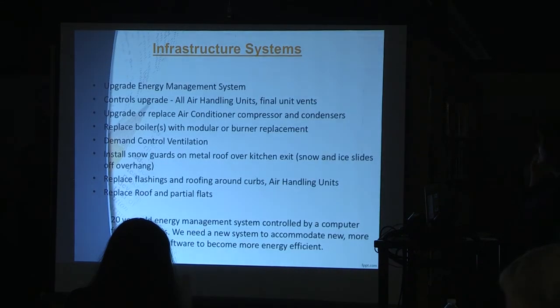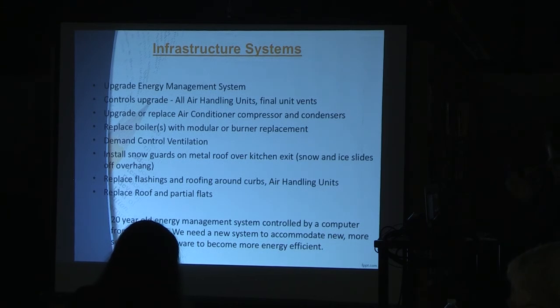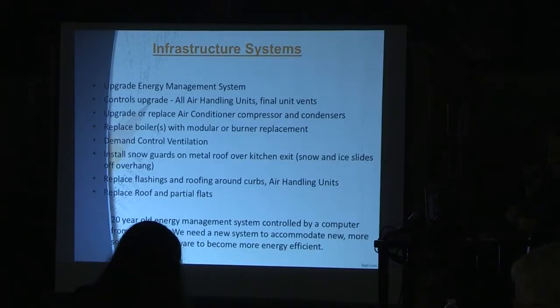Looking at the systems, we need to upgrade our energy management system because it's 20 years old and controlled by a computer from the 1990s. We need a new system to accommodate more sophisticated software and become more energy efficient. We need to upgrade the controls for the air handling units, upgrade the air conditioning compressor and condensers, replace at least one boiler with a modular or burner replacement, and work on the demand control ventilation.